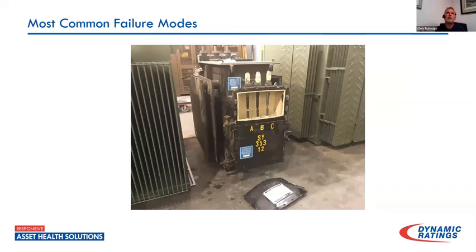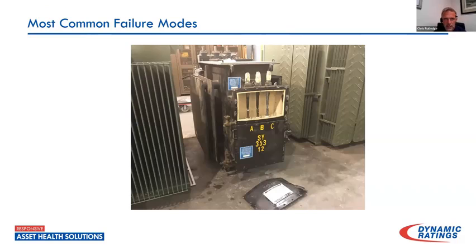Generally when we talk about transformer monitoring, we're looking at main tank — that's most of the concern. Most of us come from a substation background, so we think main tank is our critical point, bushings are another critical point, and LTC monitoring is probably the third most important. With these transformers, the failures I was seeing were very rarely main tank failures.